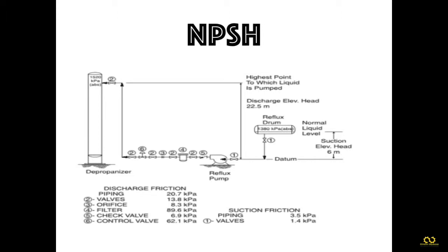According to the formula, we need to calculate the static suction head. The reflux drum is the suction reservoir. From this drum it reaches the pump, and the distance between the pump datum line and the location of the reflux drum is vertical, located above the centrifugal pump. This distance is called Hs, given as 6 meters.